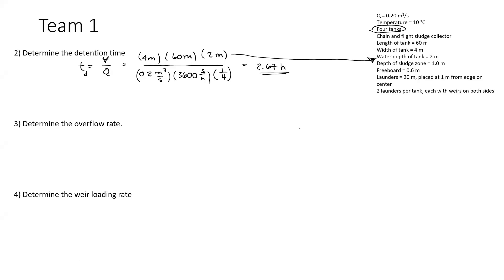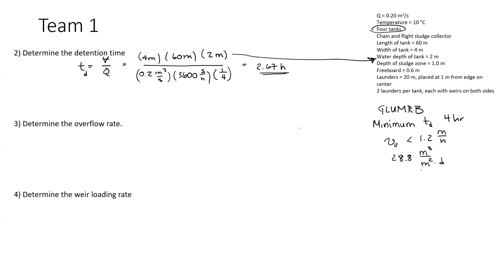Typically with sedimentation, your detention time will be in hours. If you look up the GLUMRB standards, the minimum detention time is 4 hours for water treatment, unless your overflow rate is less than 1.2 meters per hour, which corresponds to 28.8 meters cubed per meter squared per day. We need to determine whether we've met that criteria. This is important for your mini design — you need to be thinking about these criteria and making sure you're meeting them.